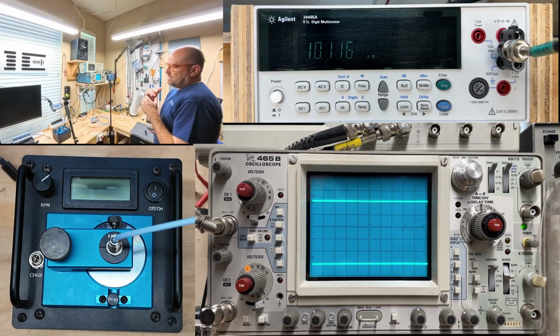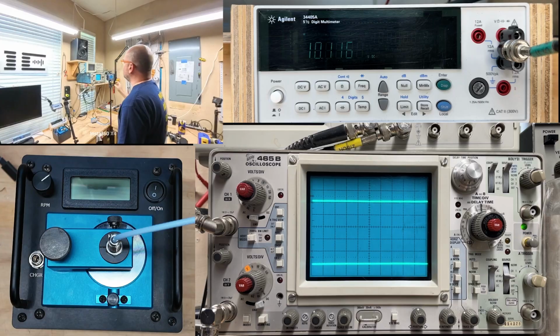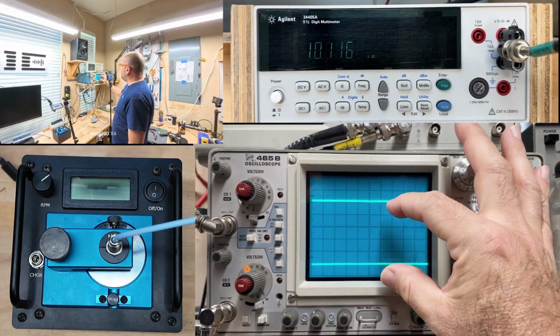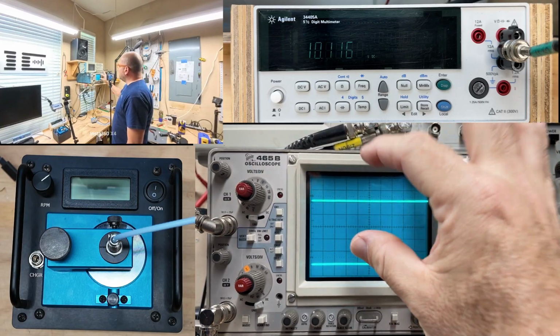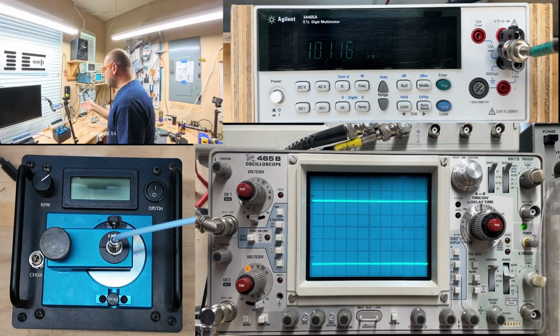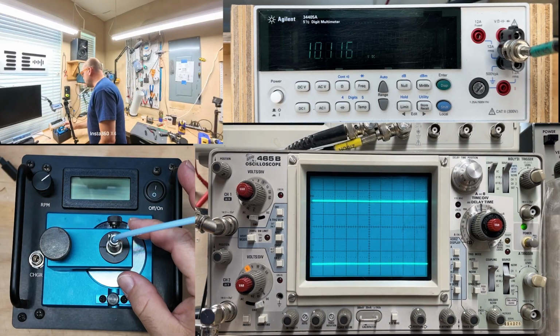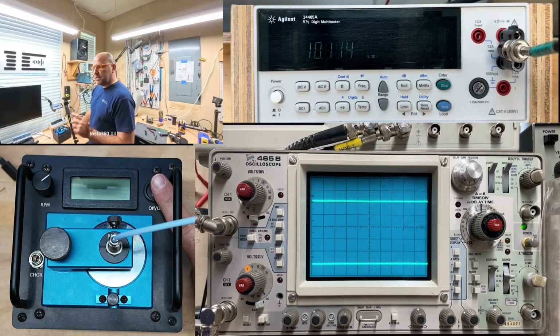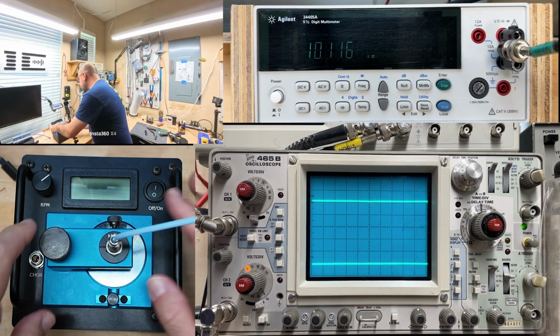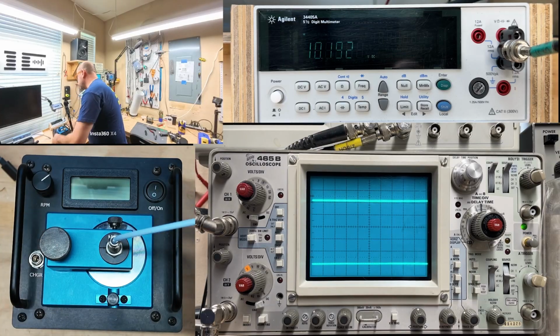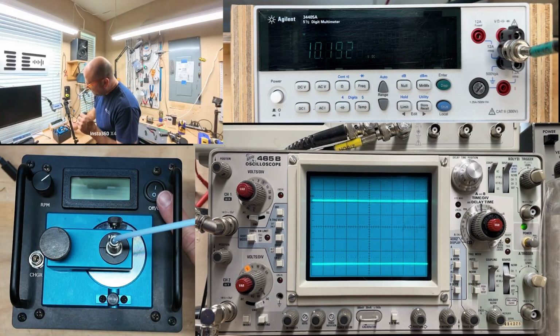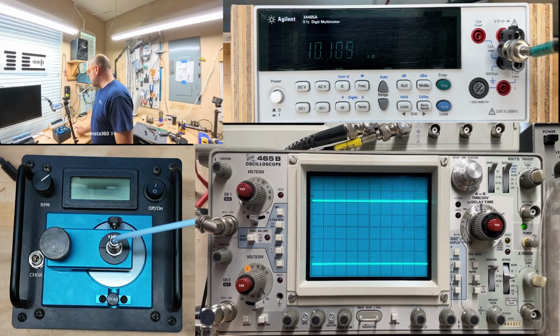Let's pretend that this is a machine. We've set the probe at 10 volts. You can see this is the distance. Basically what my oscilloscope is showing is a 10 volt gap between the probe and the metal, and it's the same that we see on the multimeter. Now, when I turn the wobulator on, at first we're not going to notice much vibration because the probe is looking at an area of the target that doesn't have that much undulation. So I'm going to turn it on.